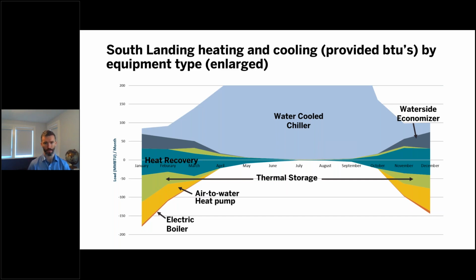So just quickly to step through how we provide heating from our central plant. Firstly, we will always dispatch heat recovery. It's the most efficient way to provide heating and cooling. Then we show thermal storage here, which typically represents heat recovery energy that is stored rather than consumed when we don't have a need to use it instantaneously. It can also represent stored energy from air source heat pump or electric boiler. Then we would dispatch the air to water heat pump and then finally our backup electric boiler.